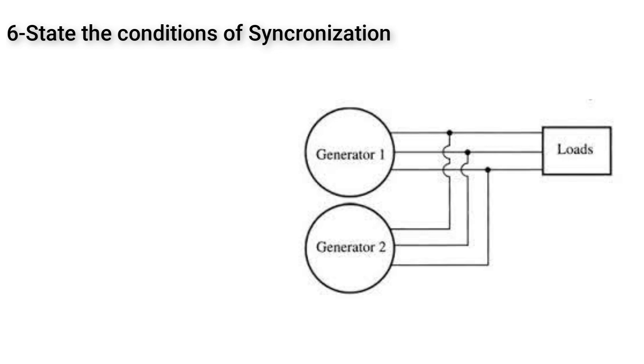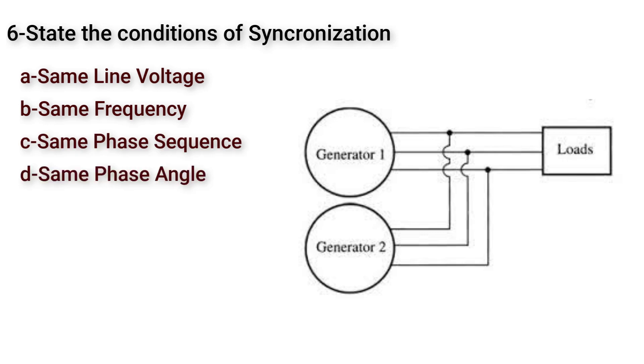State the conditions of synchronization. Well, there are five conditions that must be met before the synchronization process take place between two different sources. Same line voltage, same frequency, same phase sequence, same phase angle, and at last same waveform.